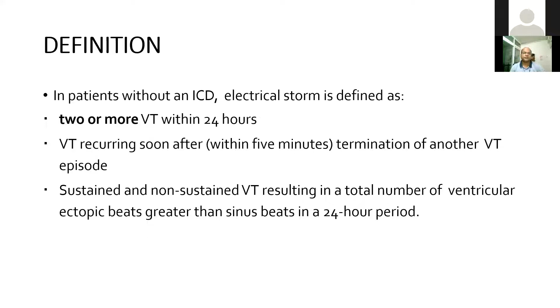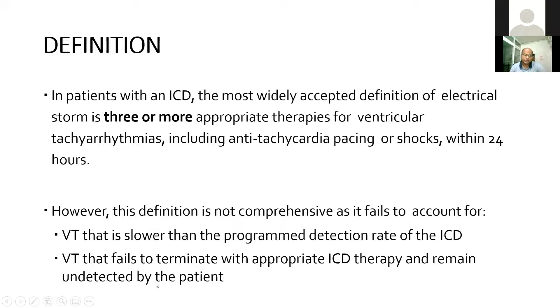However, this definition is not comprehensive, because if we look into the programming of an ICD, an ICD has a set limit for a heart rate. Suppose I program the ICD at 150, then any episode of tachycardia that goes below 150, suppose there is a slow VT where the peak heart rate is less than 150, then the ICD will not pick up those arrhythmias. It will just discard them. So that is one of the drawbacks: when the VT is slow, the ICD will not detect it. And VT that fails to terminate with appropriate ICD therapy and remains undetected by the patient is also one of the problems that can be missed.